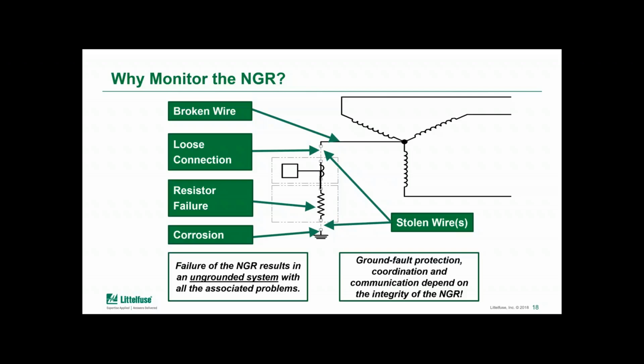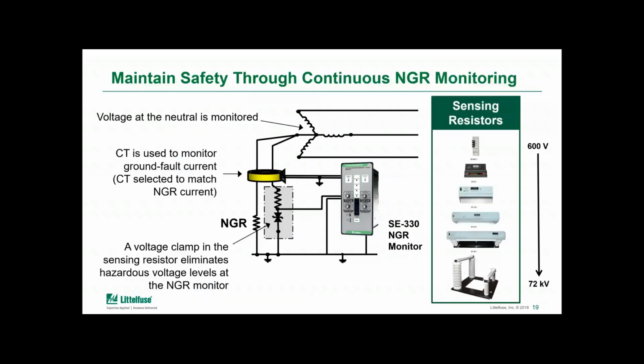Now, if you have a system with a broken connection somewhere in there, the system converts to an ungrounded system. And that brings along the risk of transient overvoltage and the things we talked about already. Something else you need to be aware of is that the ground fault protection on the system that is normally looking for leakage current will also fail to detect a fault because there's no longer a return path for that fault current. So in that case, there's another engineering control that we can use to mitigate that risk.